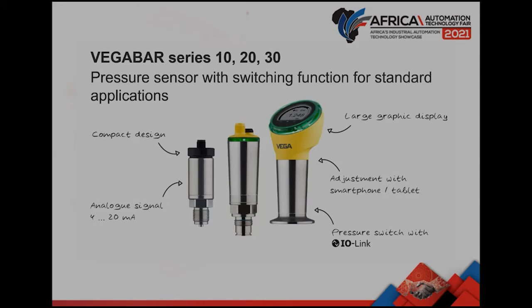And on the slide, we can see that there's a range of compact devices that have been developed. So look on the first option, that's a fixed range pressure transmitter. It's a VEGABAR 10 series. Then we have the VEGABAR 20 series, which comes with an LED light indicator, and the VEGABAR 30 series with a ring LED as well, with a local display also to indicate the pressure. It has onboard functionality on the display to make parameter adjustments and do a complete setup of this device.